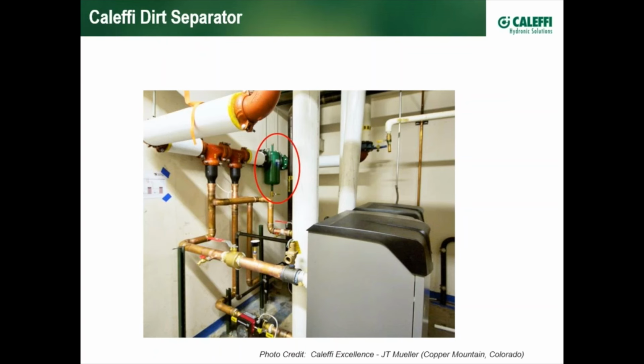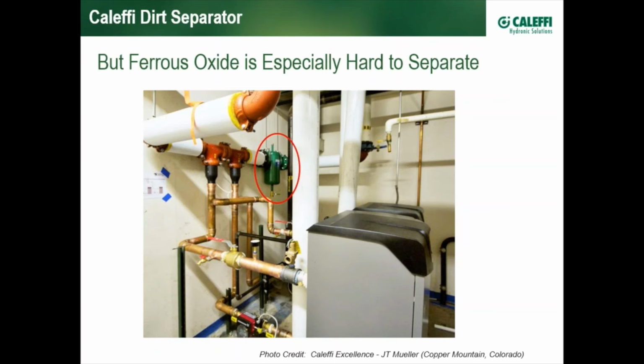There's also Taco and Spirotherm that make this type of product in the marketplace, and they are all very effective. However, one issue all manufacturers have faced over the years is a type of debris called iron oxide or ferrous oxide. It's the result of oxygen reacting with any steel or iron in the system, such as a radiator, or even the pipe itself, to create iron oxide, sometimes known as magnetite or hematite, depending on the form it takes within the system.